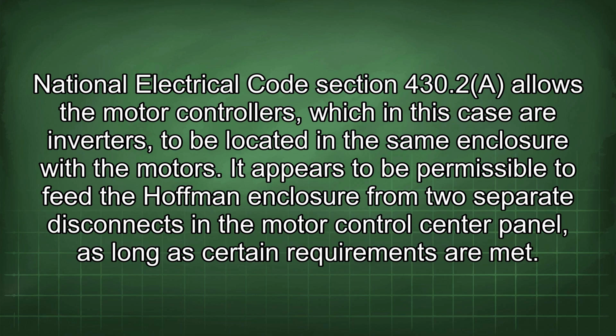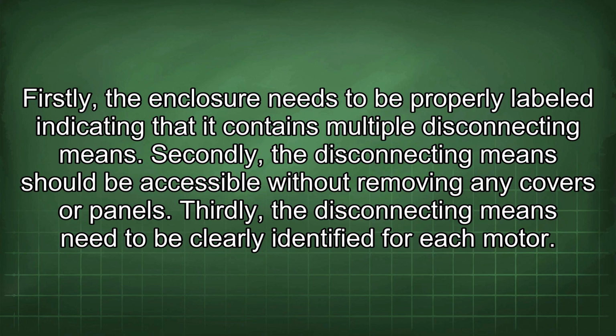It appears to be permissible to feed the Hoffman enclosure from two separate disconnects in the motor control center panel, as long as certain requirements are met. Firstly, the enclosure needs to be properly labeled, indicating that it contains multiple disconnecting means. Secondly, the disconnecting means should be accessible without removing any covers or panels. Thirdly, the disconnecting means need to be clearly identified for each motor.